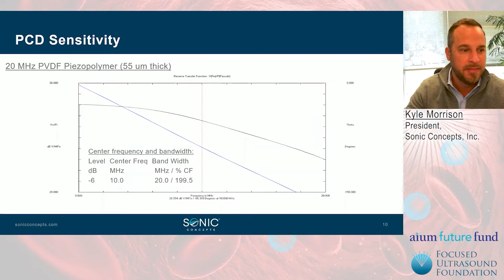Here's an example of PCD sensitivity with focusing. So to give you an example, an unfocused sensor will reach its transition plane at D squared over 4 lambda. The diffraction patterns up until the transition plane will vary in phase between an amplitude of 0 to 1, where 1 is the amplitude at the surface. When focusing an aperture, we increase the focal gain, which you're seeing in blue, which forces the field of which it's sensing to begin diverging at the acoustic maximum. So in this case, when expecting emissions around 2 megahertz, using a spherically formed concave surface with a 63 millimeter radius, we actually increase the sensitivity by a factor of 6. So 38 times 6, we're at 228 volts per megapascal. So that's extremely high at 2 megahertz.